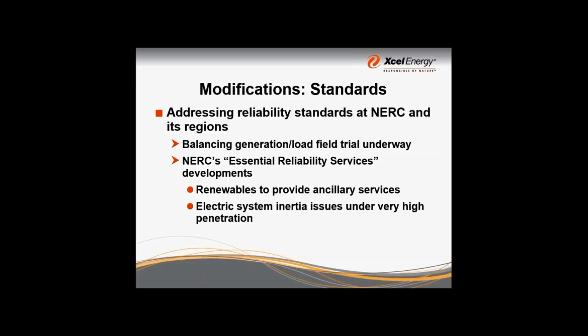One last thing I forgot to put as a bullet: there are different standards for a concept Mark mentioned called ride-through—the ability of a renewable resource to stay connected to the grid during a disturbance, say a lightning strike. Right now there's a standard for distribution-connected utilities called IEEE 1547, under which distribution-connected resources are supposed to trip offline. But at the NERC standard level for the bulk electric system, resources are supposed to stay online and ride through. So there's an important industry standards effort underway to reconcile these 180-degree conflicting requirements on interconnected resources. This might be an area folks are interested in pursuing further.